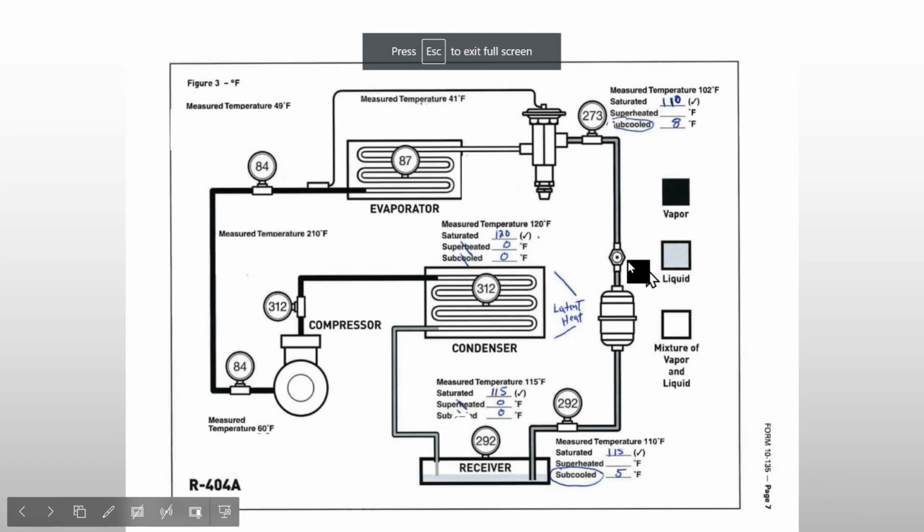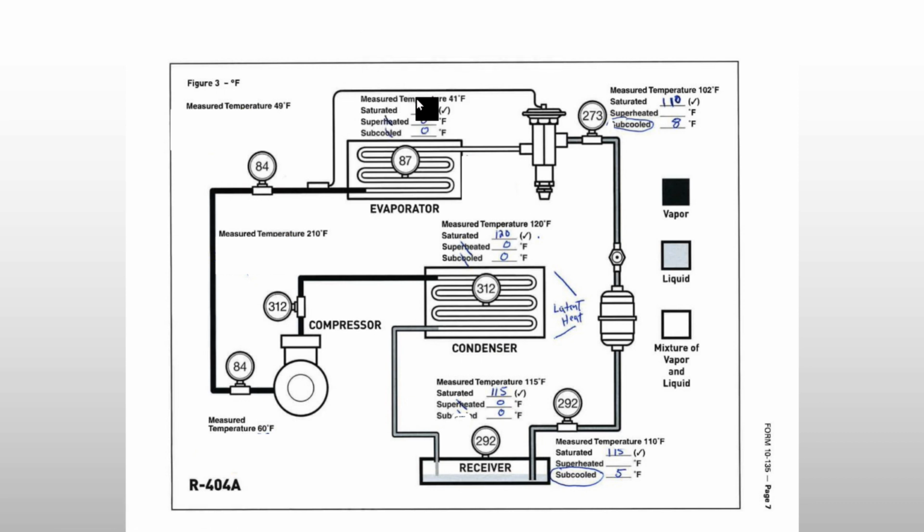Glad I caught that. So 41, and the measured temperature is 41. I have 0 degrees difference, so I'm not superheated, I'm not subcooled. What I am is a mixture of vapor and liquid together. I'm saturated. So that's where I need to be.